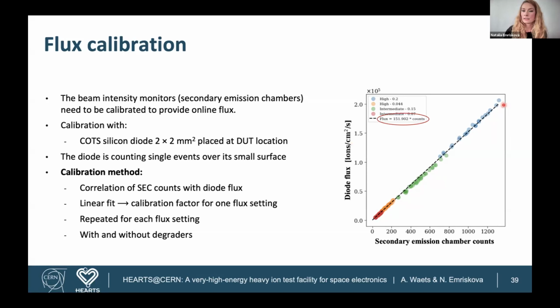Then we make a linear fit and we can extract the calibration factors that you see here. And we do this for all the different flux settings, which is represented here in the different colors. Of course, we also have to do the flux calibration with and without degraders, because if you put in place the degraders, the flux count is attenuated, and this has to be corrected.